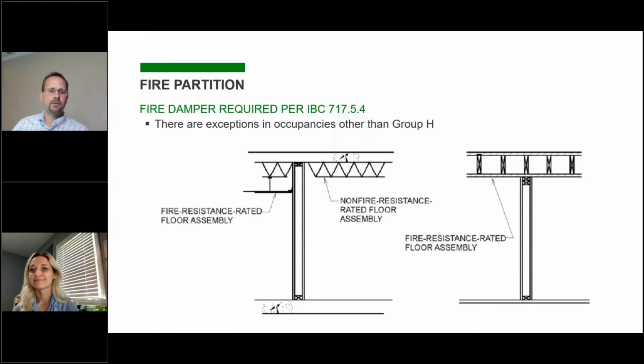Yeah, and so damper requirements for a fire partition are very similar to a fire barrier, except there's a little bit more leeway and more exceptions that apply. The same exception verbiage for the fully ducted system is still in the code for this one, but they have other exceptions: if you're in a corridor wall in a 1 hour that has a sprinkler system, you don't have to have any dampers. So a lot of buildings that maybe previously weren't sprinkled, but then became fully sprinkled, you may have differences where you'll have fire dampers in a corridor, but in a newer expansion where they sprinkled, there won't be fire dampers in those corridor walls.